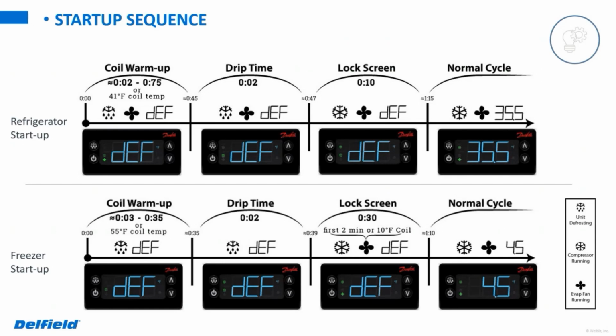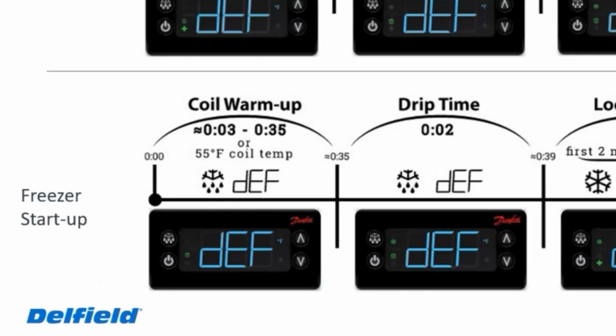So as far as the freezer goes, it's a similar setup. We're going to have a minimum and maximum amount of time that the unit would be in defrost, but we're also looking for that coil temp, and in this case it would be 55 degrees. So under normal operation, you're probably looking at a defrost lasting about 15 to 20 minutes or so for a freezer. It'll show that DEF on the display. It'll have the melting snowflake on the outside of it, no fan on.